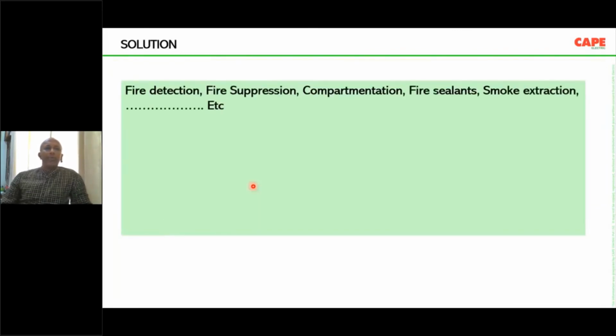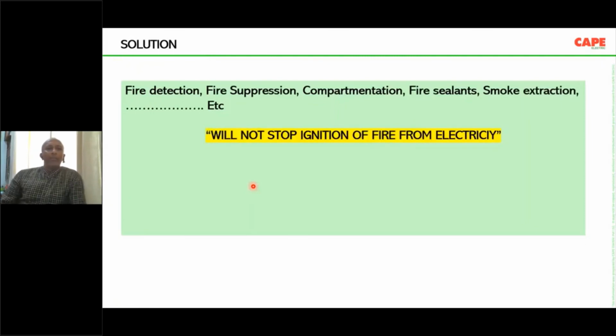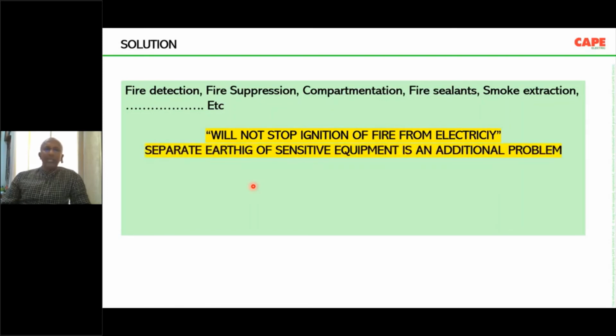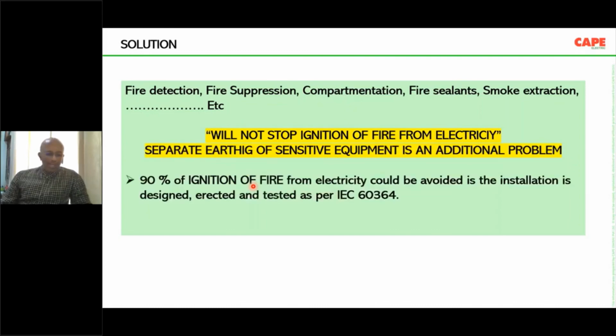What do we do? First, we should understand that fire detection, fire suppression, compartmentation, fire sealants, smoke extraction, all these safety measures, of course, are highly essential for a building, but these measures will not stop ignition of fire from electricity. And the separate earthing of sensitive equipment is an additional problem. 90% of ignition of fire from electricity could be avoided if the installation is designed, erected, and tested as per IEC 60364. I have explained two cases.